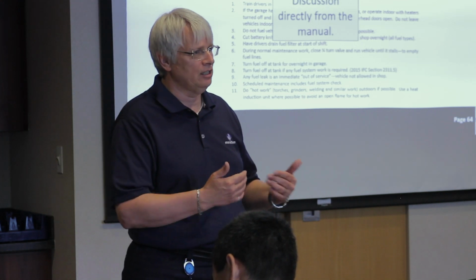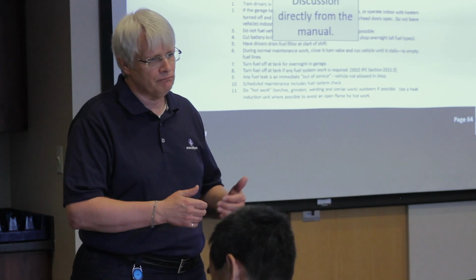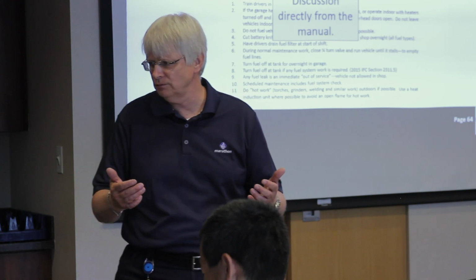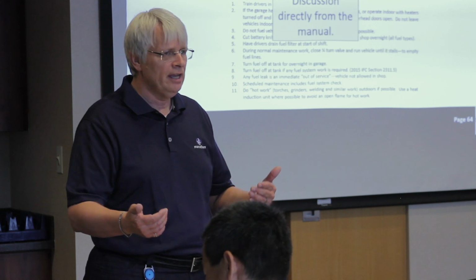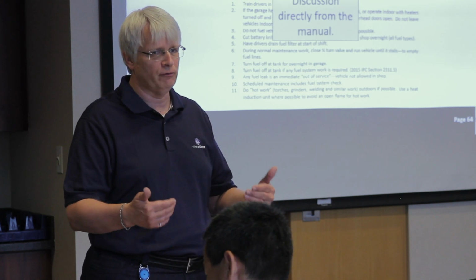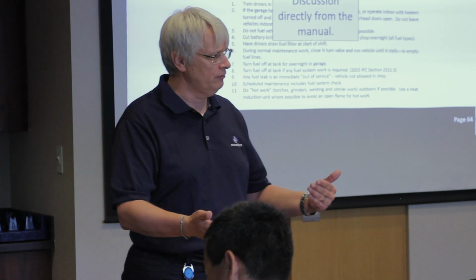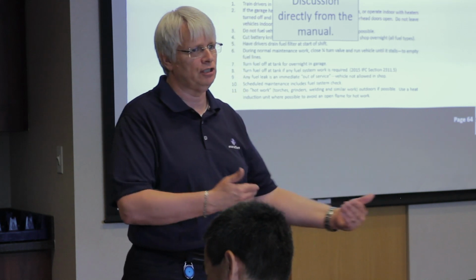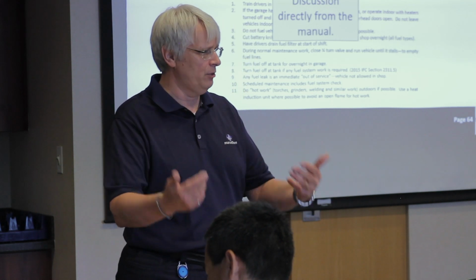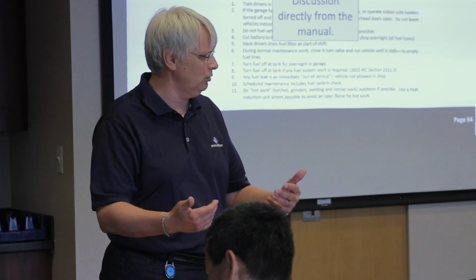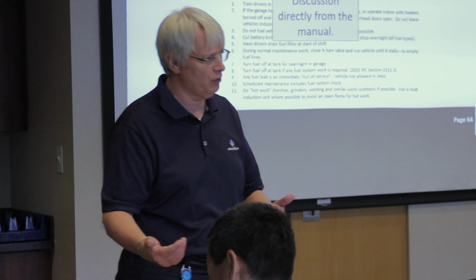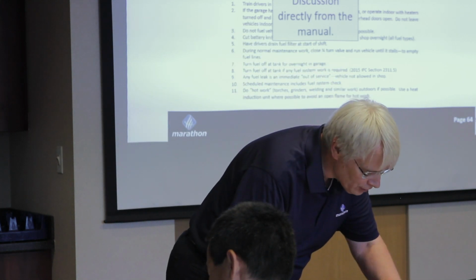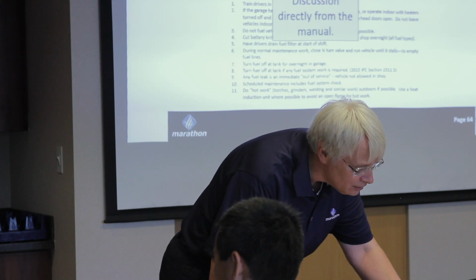As he said, they got into CNG, I'm not sure how many, 7 years ago? Yep. 7 years ago. And then the last 2 years, they've also added hydrogen. It was a pretty easy transition for them because they had done the facility upgrades when they went from diesel to CNG. And then really the only upgrade, I think, was the gas detection system to move them towards hydrogen as well.